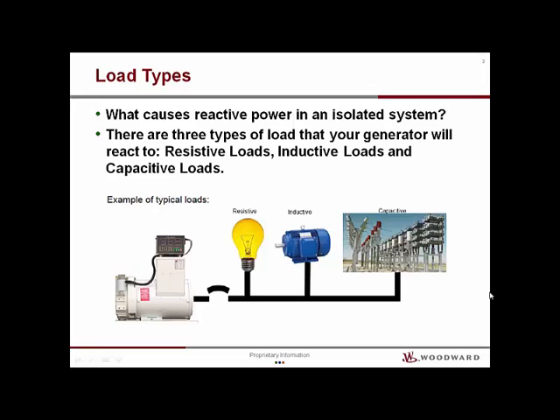Inductive loads are inductors or coils that usually consist of induction motors, fluorescent light ballasts, and anything with a coil of wire inside of it. Inductive loads will create a lagging power factor. Capacitive loads are not very common, as there are not many physical devices that are capacitive, except a capacitor. Synchronous motors can act a little capacitive. Capacitive loads will cause a leading power factor.